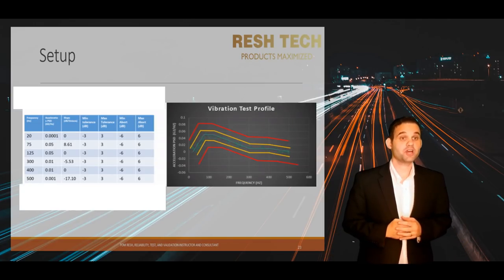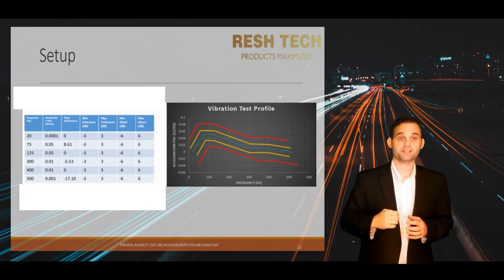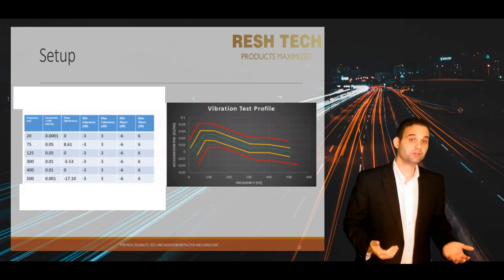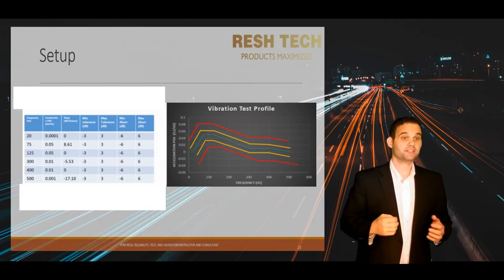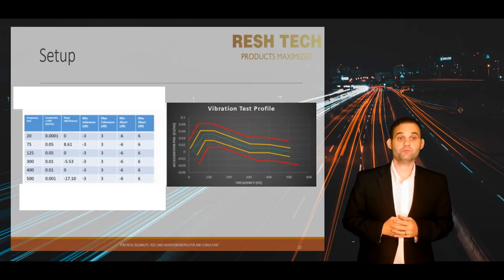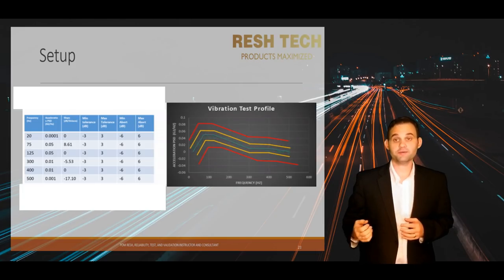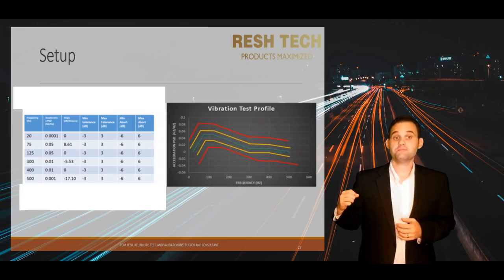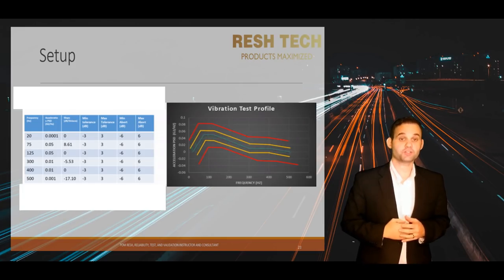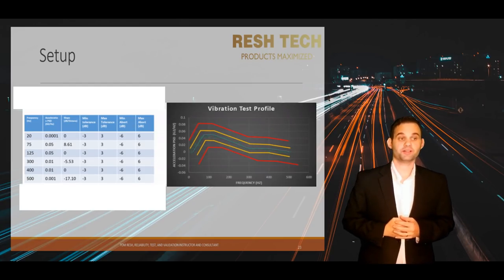Let's cover the test profile menu. The test profile menu has a breakpoint table, and notice there are a few additional columns: slope, minimum tolerance or limit, maximum tolerance or limit, minimum abort, and maximum abort.